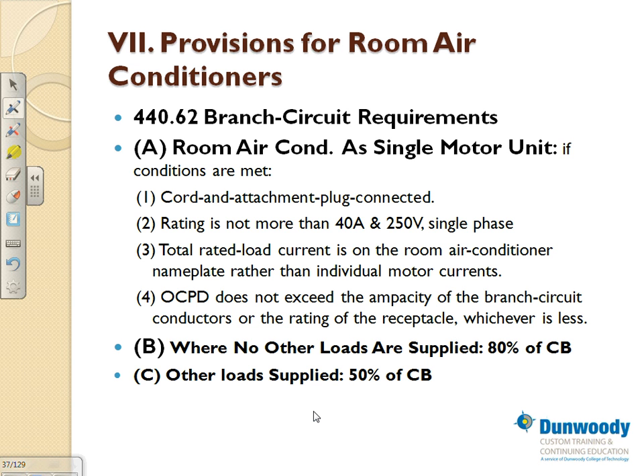If you have a dedicated circuit, and we use it all the time, guys, you know how much is related. Suppose you have a circuit breaker and a 20 amp circuit. If you have a dedicated circuit for a window air conditioner, and you're plugging it in right here, then you're limited to 80%. So on a 20 amp, your air conditioner shall not be more than 16 amps, right? Plug it in, dedicated circuit, one receptacle, 20 amp circuit breaker, you're limited to 16 amps. If the rated load amps on the equipment is 17 amps, you can't feed it from a 20 amp.